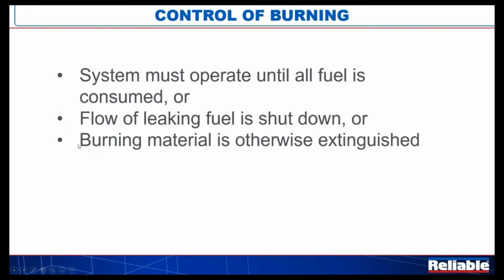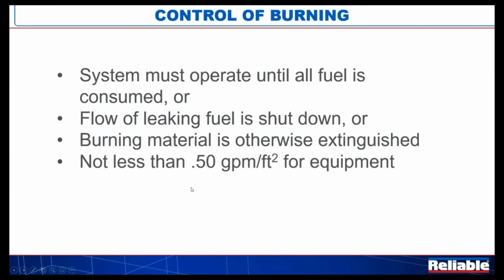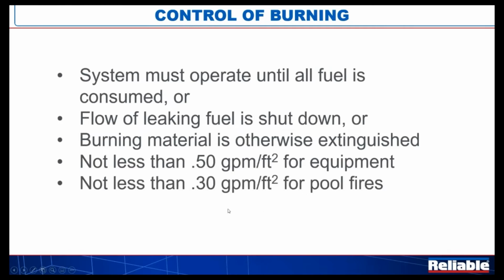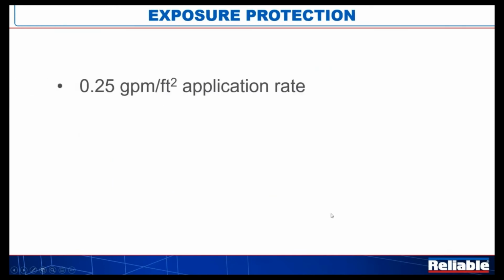So again, these are some really nebulous concepts here, but it's apparently the best that we could come up with in terms of the committee language for these open tanks. Not less than 0.50 GPM for the equipment, which is where the fire is likely to be started. And then if the pool is just simply sitting there, we want to put a 0.30 GPM density over the top of the tank, or what they call the pool.